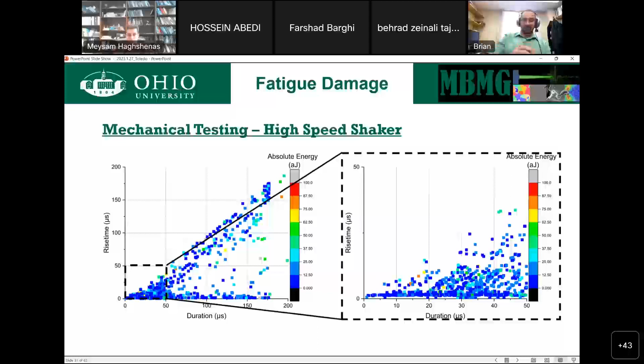So I've shown this plot a few times. At this point, I want to emphasize why. This is rise time versus duration. Rise time is how fast the wave reaches its maximum value, and duration is how long it goes from when you first see it to when it stops. For a lot of materials, if you're looking for a fracture event, that should be a fairly fast event. It should not take long to reach its peak, and it should not take long to die back down.